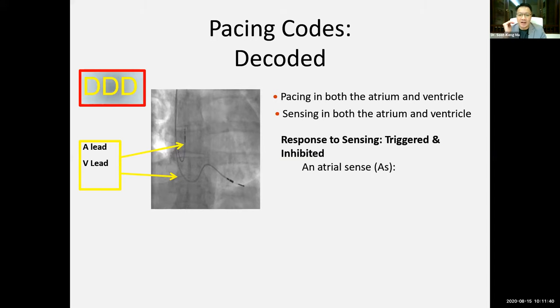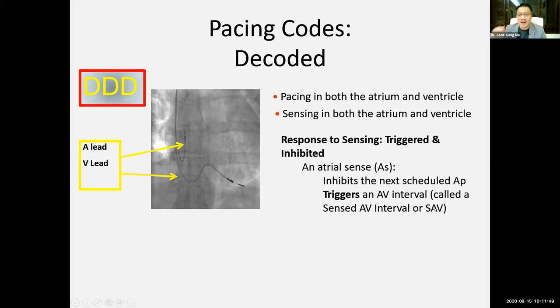If you have an intrinsic atrial sense activity, atrial sense means you detected intrinsic activity in the atrium, you need to trigger the pacemaker, because you need to initiate another internal clock timing cycle called the AV interval. So the clock will tick until it times out and it will look for cardiac electrical activity or initiate another clock.